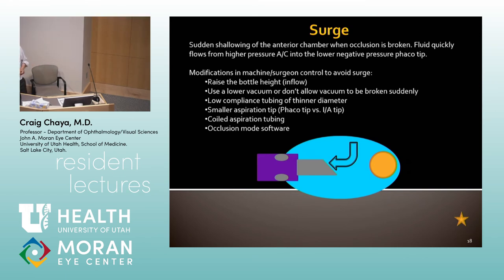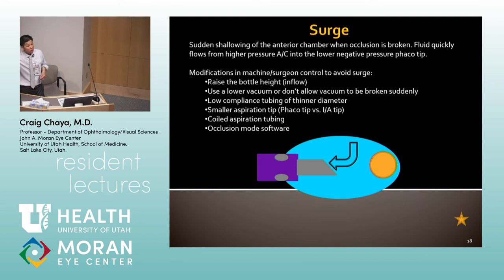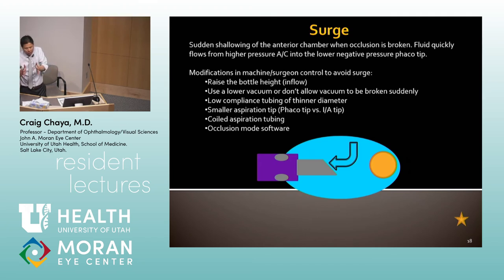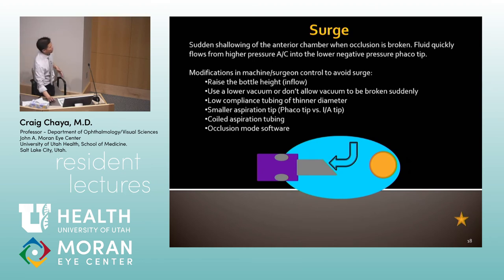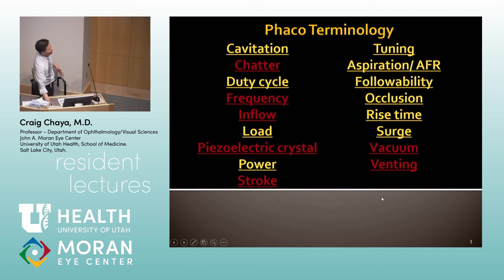On the new machine there's pressurized infusion. The Centurion doesn't have a hanging bag — it goes into a container with two walls that come together and squeeze the bag, which is why we use soft bags. When using the Infinity, we're using glass bottles, but here the soft plastic bag is squeezed together to actually pressurize infusion inside the eye.